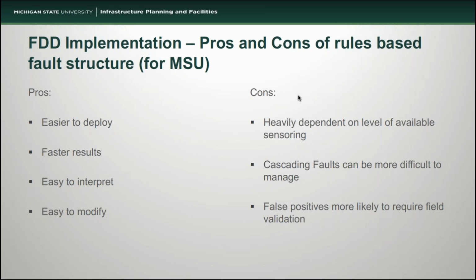And because it's a relatively simple language to implement, they're easy to modify. So if we have a unit where the accuracy of our temperature sensor is 2 degrees, we take that half-degree fault and change it to 2.5 degrees so that we would expect to see a change. And that's really pretty simple with a rules-based fault structure. The downside of a rules-based fault structure is it's heavily dependent on the level of available sensoring. I cannot detect a fault based on information that I can't collect because I don't have a sensor there to collect that data. Also, cascading faults can be more difficult to manage.